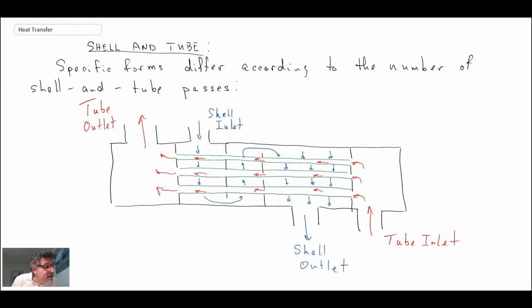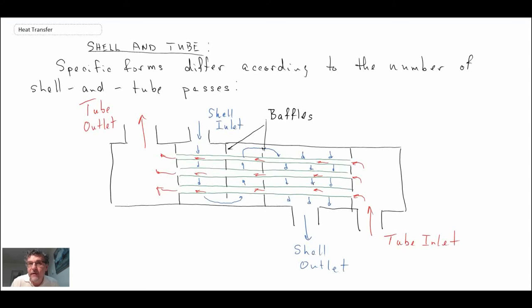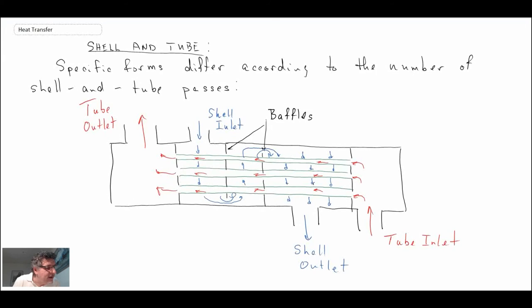In the construction there are plates called baffles or baffle plates, and there are different designs including helical patterns for more efficient mixing. From a fluid mechanics standpoint, there will be significant separation and pressure drop downstream of the baffles. Pressure drop is usually not the main concern since a large pump is circulating the fluid, but separated flow downstream of the baffles can minimize heat transfer in those regions.